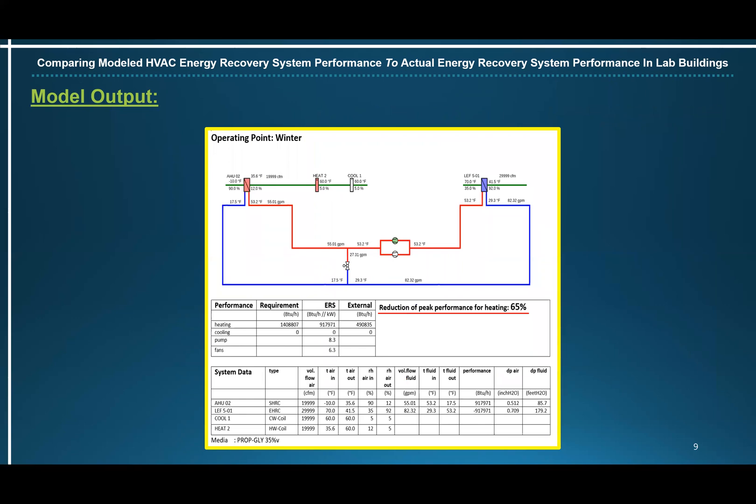And one last slide of output. This shows the reduction in peak heating requirement — you can see that it's reduced by 65%. Knowing this, you can properly size boilers, taking into account the 65% reduction in peak heating demand.